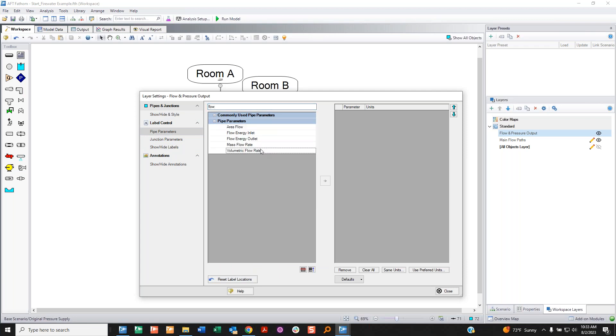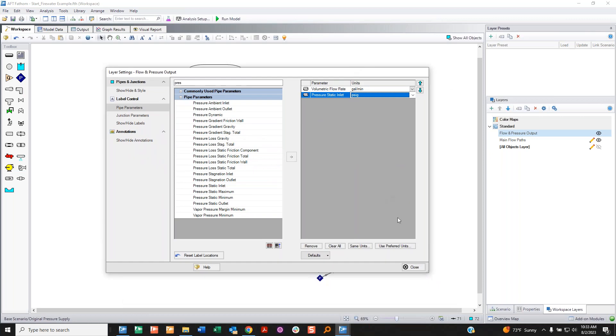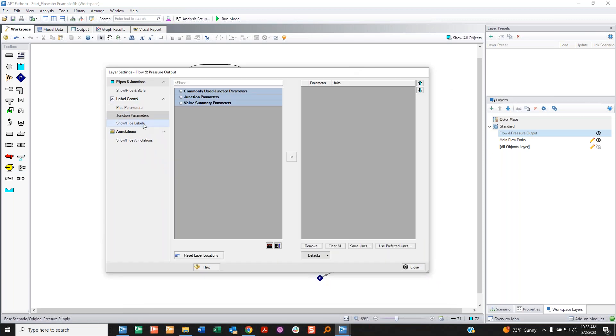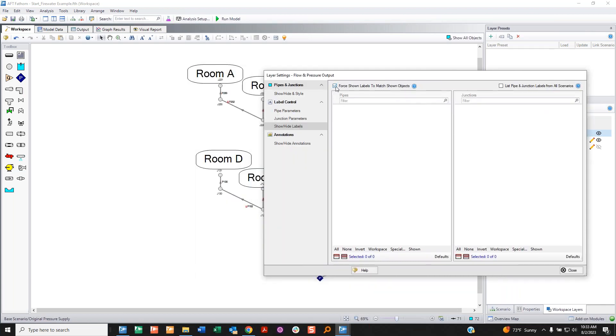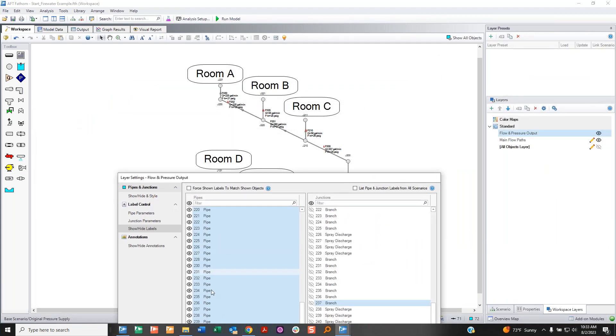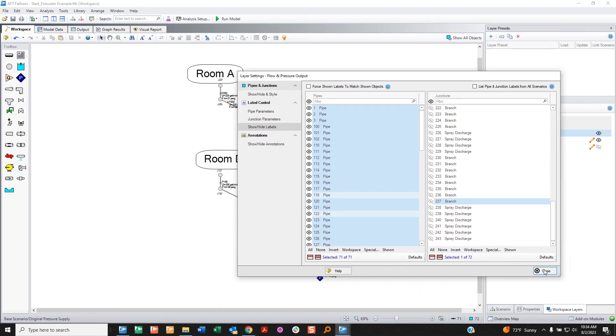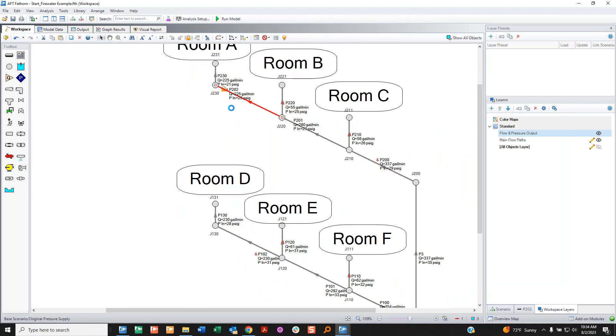Opening the settings on this blank layer: I don't want to show any pipes or junctions since I'm already showing them in 'main flow paths.' But I do want to show labels, so in pipe parameters I add volumetric flow rate and static inlet pressure in gauge units. For the show-and-hide labels section, I uncheck the box because if it's checked, nothing would show since I'm not showing any objects in this layer. I uncheck and select to show output on all pipes.